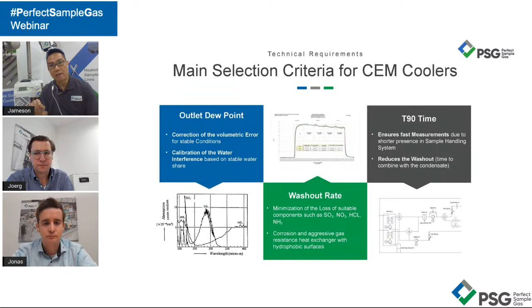Absolutely, and again this topic generalizes and may vary from region to region. When we talk about emission, we talk about RATA, relative accuracy test audit. In this area we want to ensure there's compliance and regulation, ensuring that the calibration gas passes through the gas cooler and reaches the gas analyzers. When it comes to T90, it's very important why a gas cooler is one of the factors, and we talk about the type of exchanger.